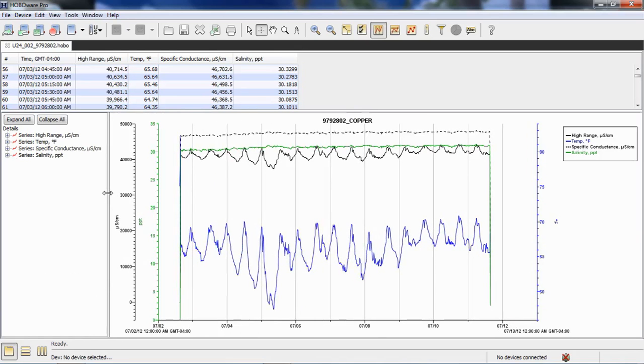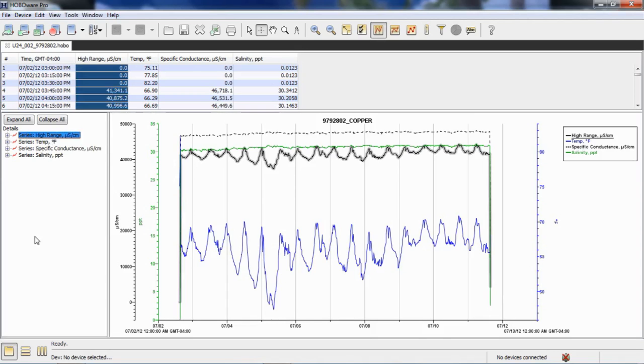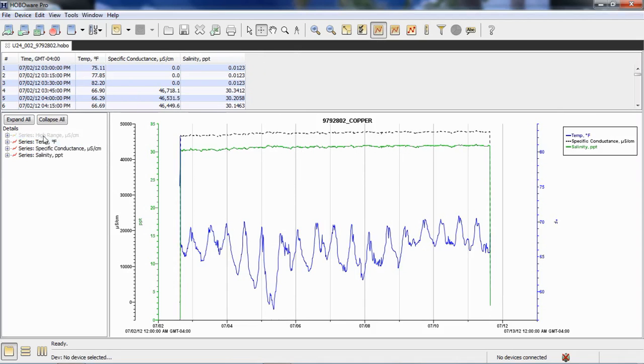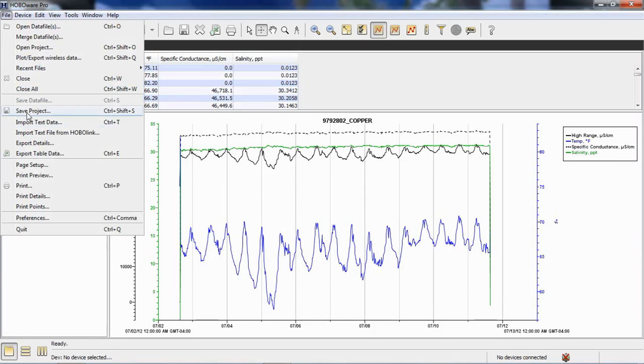So, there's my data over the deployment. We can see from the beginning of the file that the logger was out of the water for a bit. And if we want to make any changes to this file, we can do colors or delete specific series. If you don't care about looking at the actual conductivity, you can right-click on this, select it, and then say hide, take it away, or you can restore it if you want to. And then once you're happy with how this file looks to you, you can go to file and save project. And then this saves this file for future reference, and you don't have to reprocess that data again. If you don't save it as a project file, you will have to reprocess it again if you want to know what salinity and specific conductance are for this deployment.